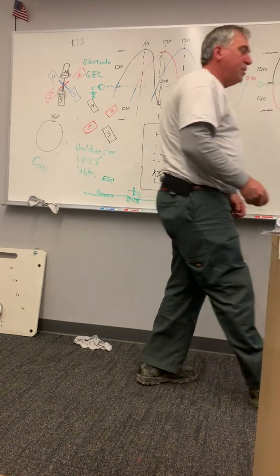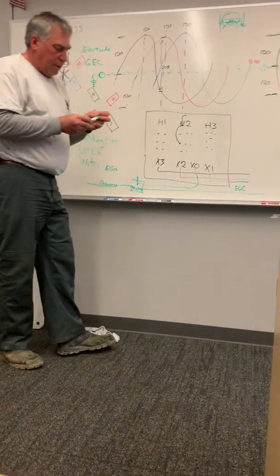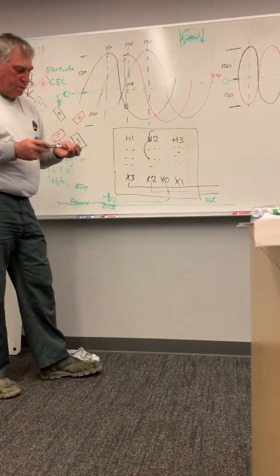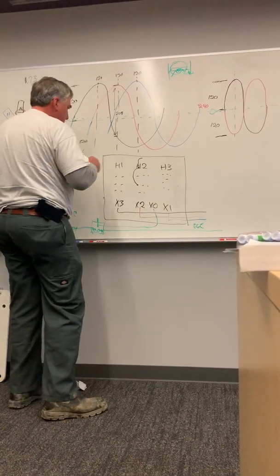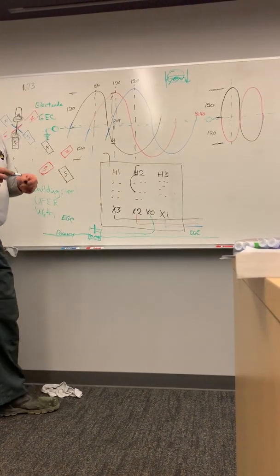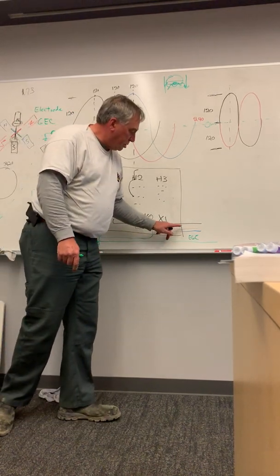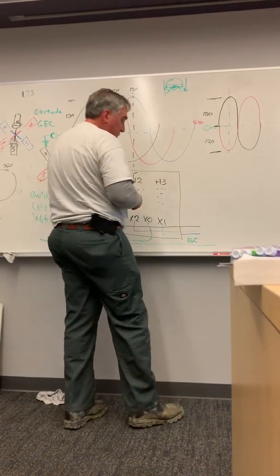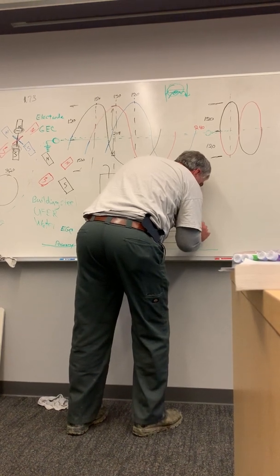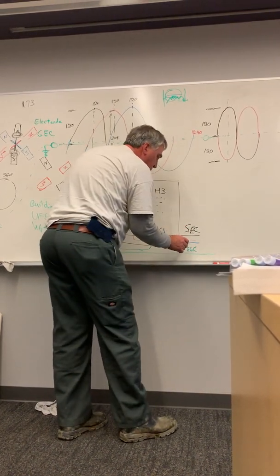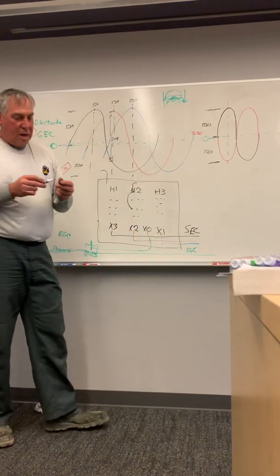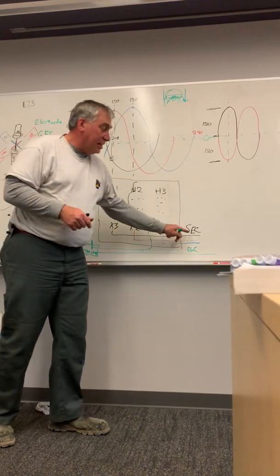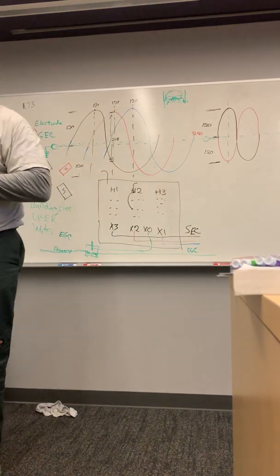So whatever this transformer is, I just hooked up a little mini 25 kVA transformer on my trailer, and it has number 8s coming into the top. That's under a 50 amp circuit breaker. But coming out of the side, I have to go to a different chart, because these conductors are service entrance conductors, right? And then you have to size them, because basically you're just trying to create this ground that will carry any fault current that size wire will create.